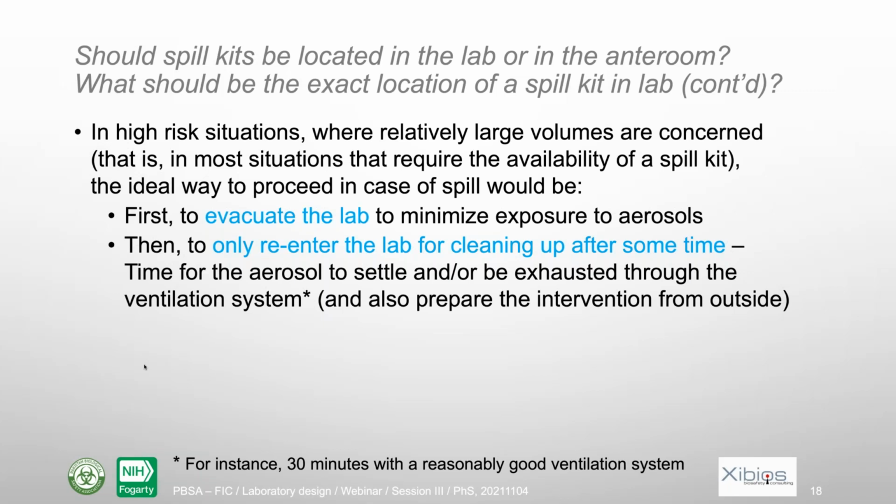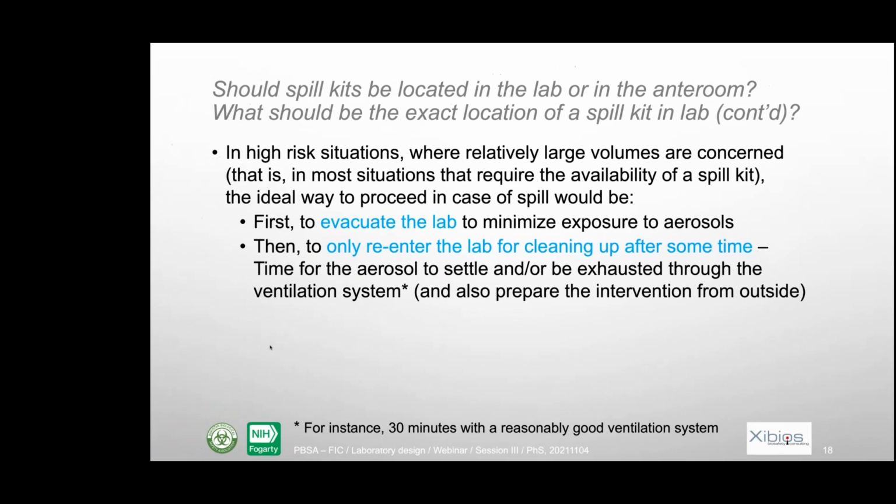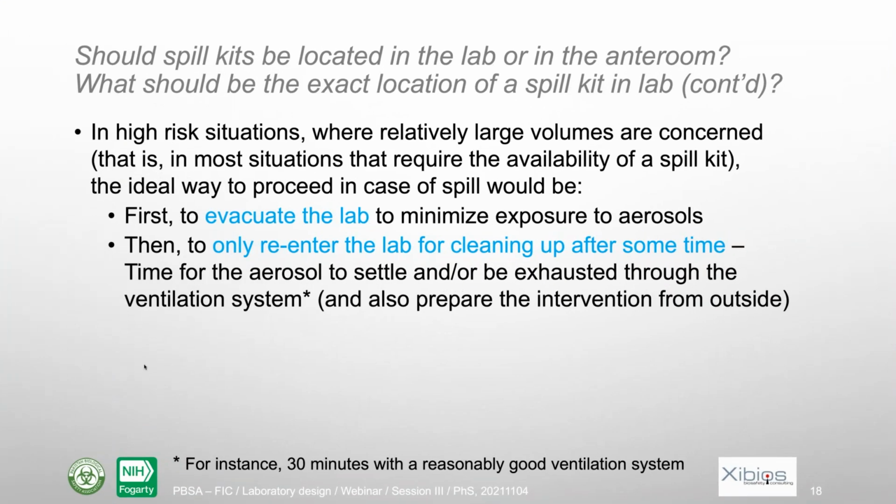The best way is to get out of the lab as soon as possible, and you leave the spill there. Okay? Then the second thing to do is only re-enter the lab for the cleaning up after some time. Why after some time? Because you need to let the aerosol settle on the floor, and that will be for the largest particles, or be exhausted through the ventilation system, and that's for the finest particles. That time could be, for instance, 30 minutes. If you have a reasonably good ventilation system, 30 minutes should be enough. But you could also wait for a longer time, okay?